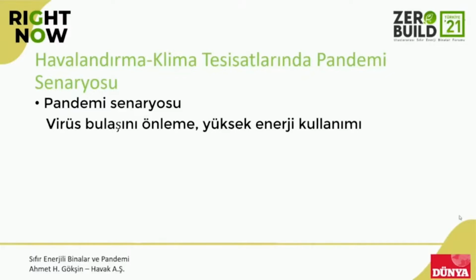If it is not possible to have an additional fan or make the fan bigger, there is the UVC system. It is ultraviolet bulbs, and they will not be calculated when it comes to resistance. There is no reason to increase the fan, but of course the UVC bulbs also increase the total energy consumption of the system. We talked about HEPA filters. I'd like to give you information regarding that.